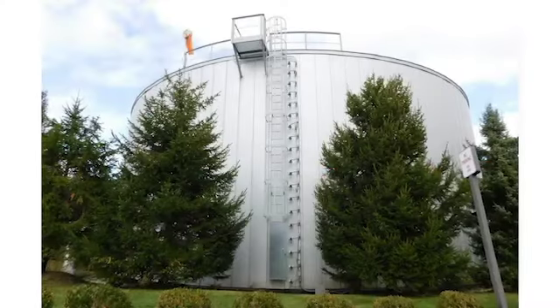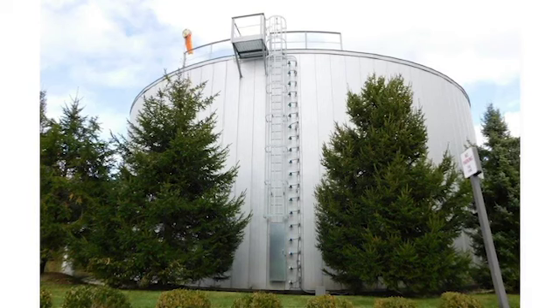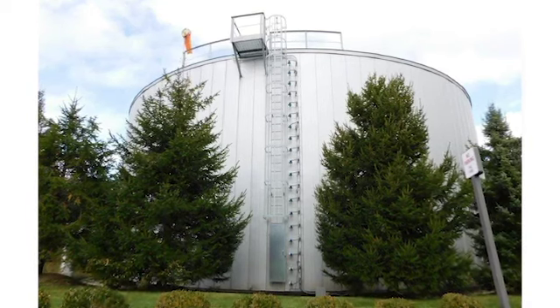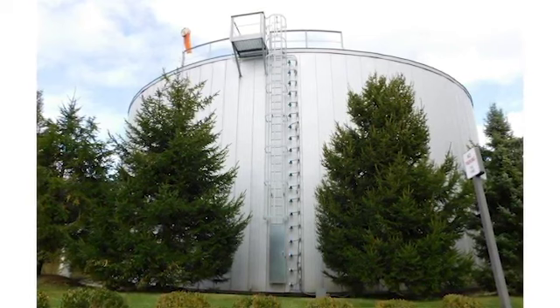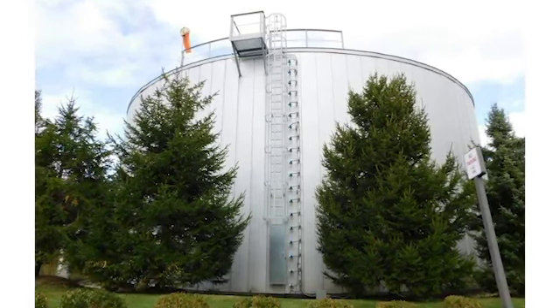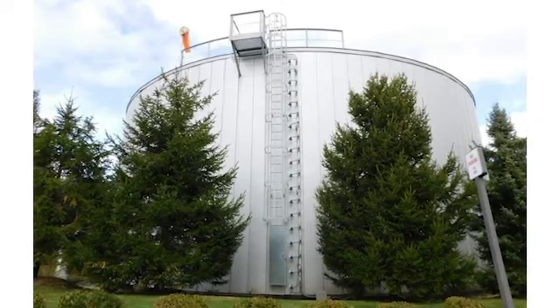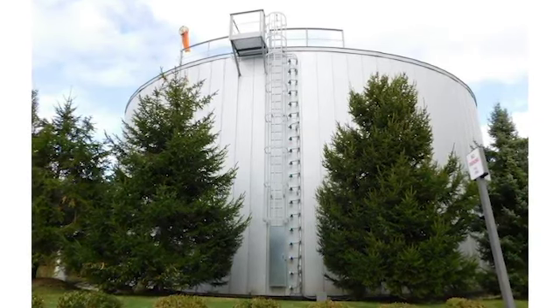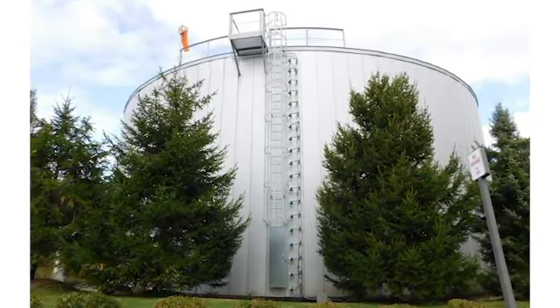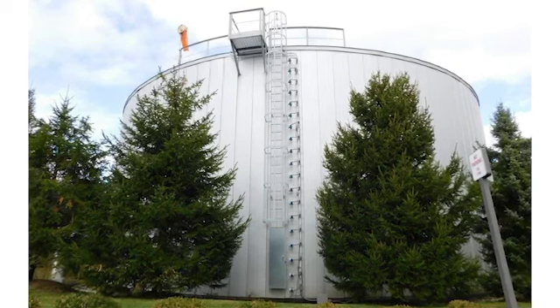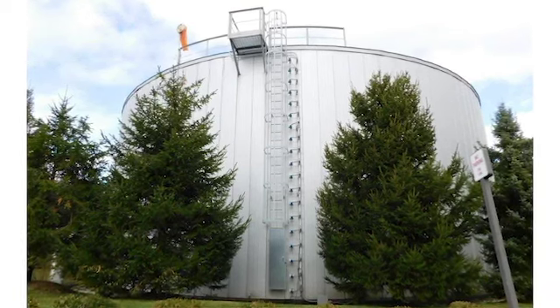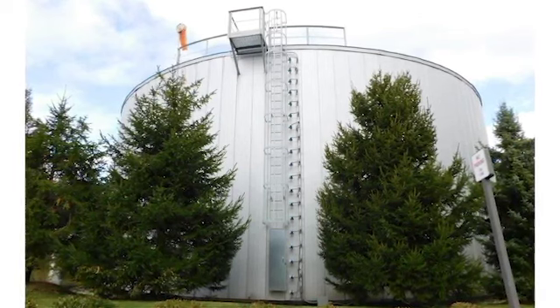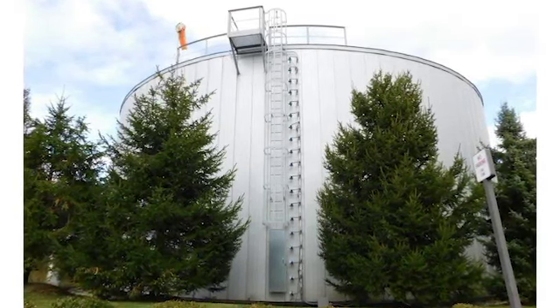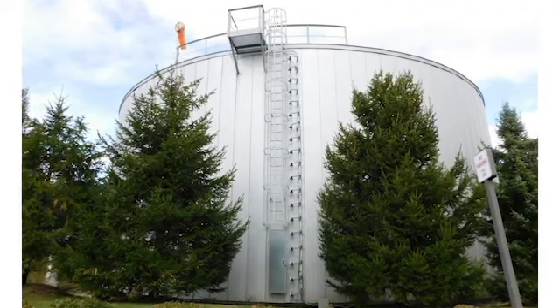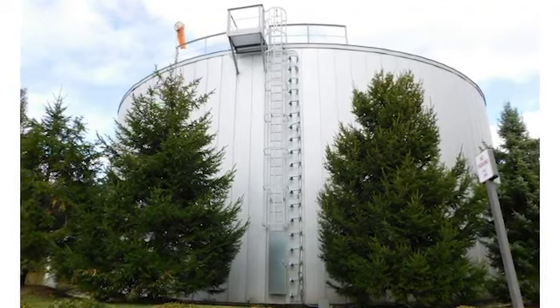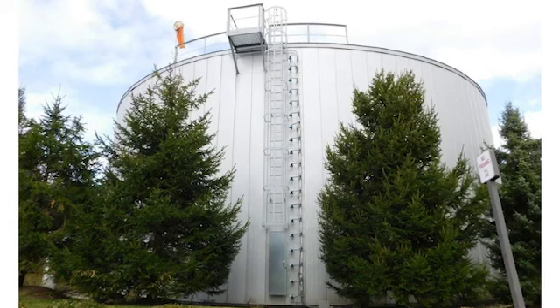We'll take a quick peek over here at the thermal energy storage tank. I mentioned that before. This is actually a 1 million gallon storage tank and works out to be about a 10 megawatt hour storage battery. That's the way I see it as the plant. When we look at it, each chiller train that we have, that's the chiller, the pumps, the fans, roughly equates to about a megawatt of energy being used. And the thermal energy storage tank, when it's dispatched, takes 1 megawatt off our load.